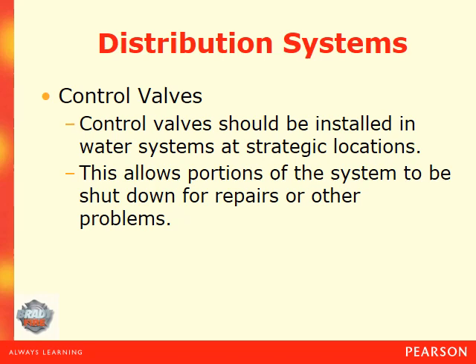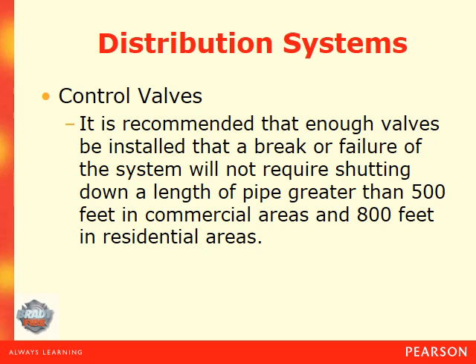Control valves should be installed in water systems at strategic locations, allowing portions of the system to be shut down for repairs or other problems without taking out the entire system. It is recommended that enough valves be installed so that a break or failure will not require shutting down a length of pipe greater than 500 feet in commercial areas and 800 feet in residential areas.